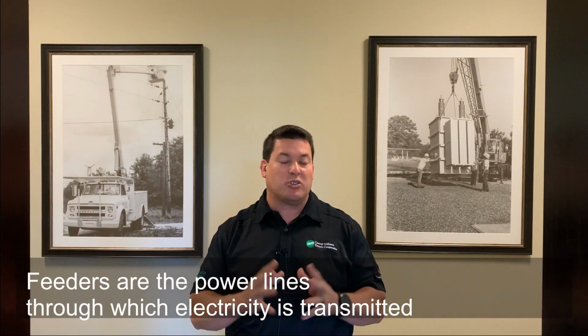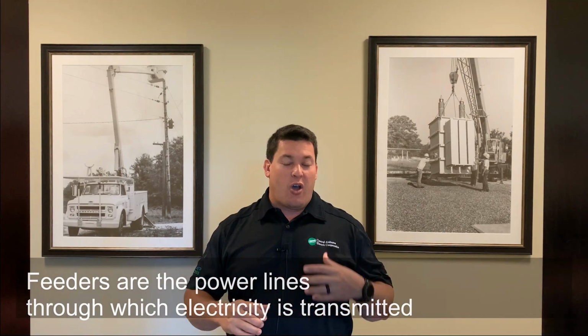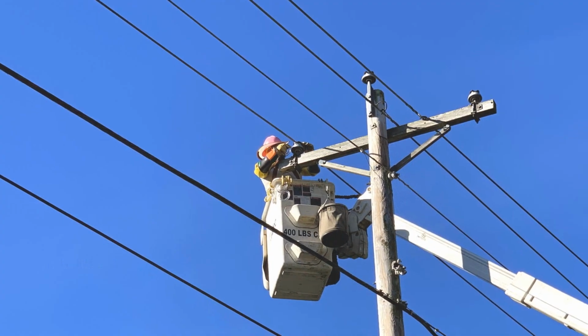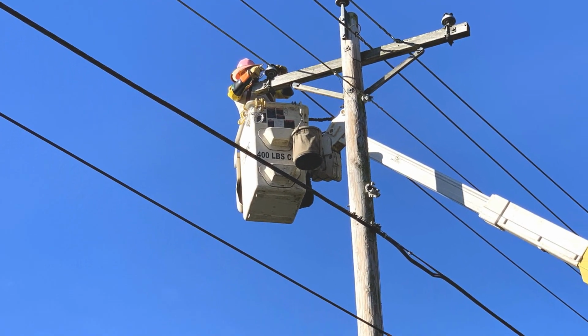Once the substation is energized, we can move on to the next part of restoration, which is working on our main feeder lines. Once we get all 24 substations up, we can begin focusing on the feeders. We're doing this simultaneously—if a substation's already up, we can immediately start focusing on its feeders.